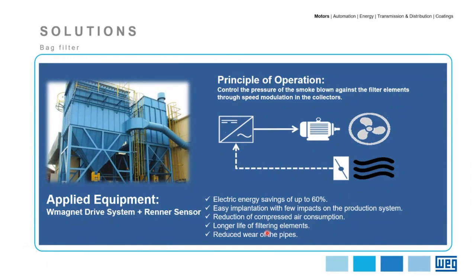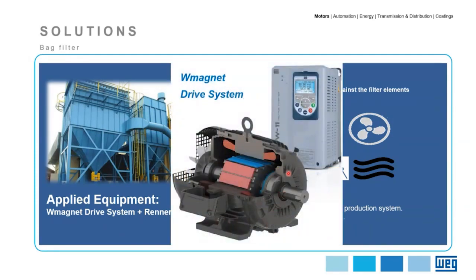This is another application found in the industrial field called a BAG filter, where the principle of operation is to control the pressure of smoke blown against filter elements via modulation in the collectors. In this application, we achieved about 60% energy savings, along with benefits such as ease of implementation with few impacts on production, and reduction in compressed air consumption. The main equipment applied was a W-magnet drive system plus a Renner sensor — meaning a WEG permanent magnet motor plus a WEG inverter suitable for such motors.